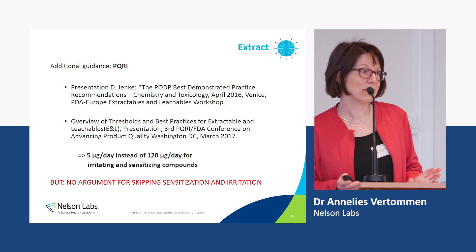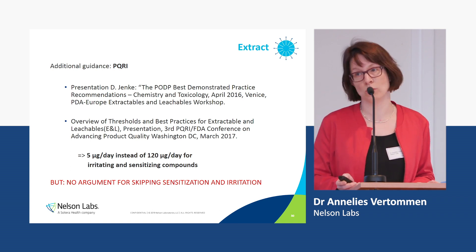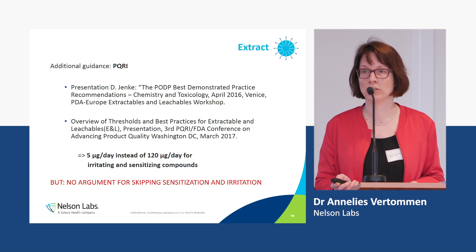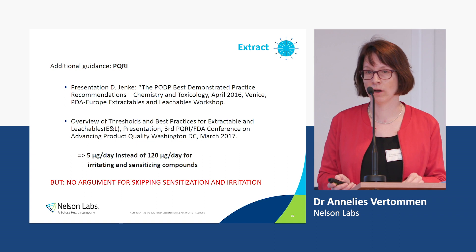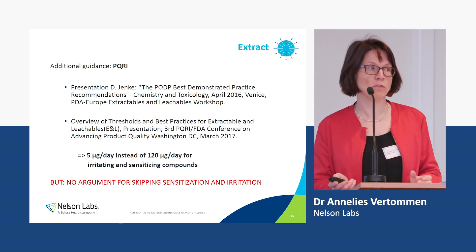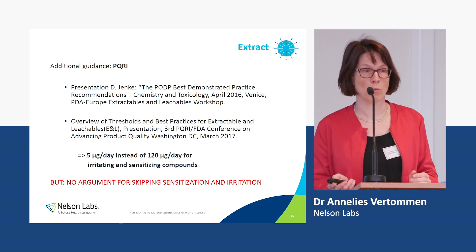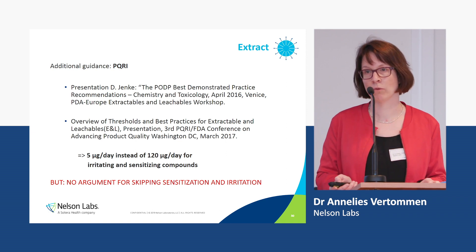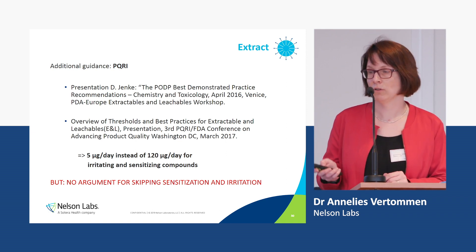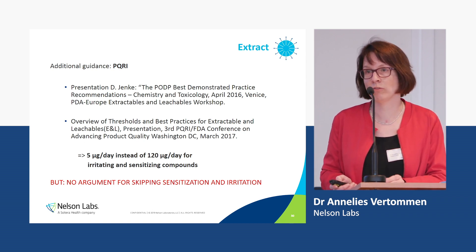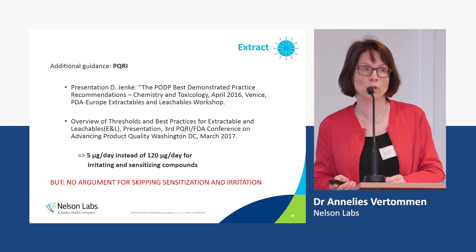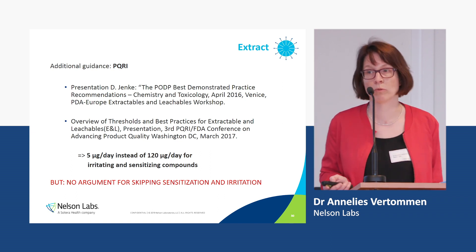You might want to lower your analytical evaluation threshold from 120 to 5 micrograms per day so that irritation and sensitization tests are also covered. However, you cannot replace sensitization and irritation testing at the moment with chemical characterization, because irritation is a local effect and it's hard to predict based on the structure of a chemical compound — an effect on one place cannot happen on another place. Therefore, you still need to do sensitization and irritation testing, even when you have done a chemical characterization using a threshold of 5 micrograms per day.